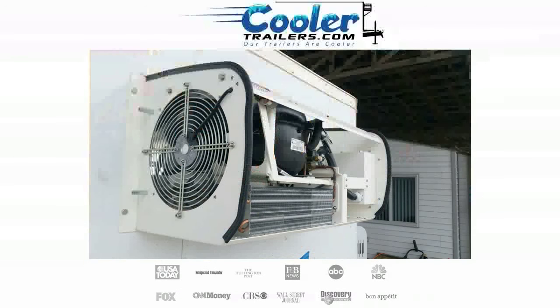The best and most effective way to defrost the evaporator coil is with hot gas defrost. The simplest way to explain this is it's like a heat pump that takes the heat generated from the working compressor and flashes that heat back through the coil internally, and in about 3 to 5 minutes, yes, in 3 to 5 minutes, you're back in business.